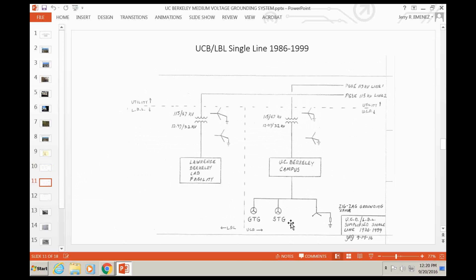That was 1986. So the cogen has a gas turbine generator, a steam turbine generator, and the question is always, how do you properly ground a cogen plant? And this is nothing that's really unusual. We've got a solidly grounded source up here at the transformer. It's usually a good idea to use some kind of low resistance grounding or resistance grounding. In this case, it was done with the assistance of a zigzag grounding transformer. That's pretty consistent with what I've seen at other places.